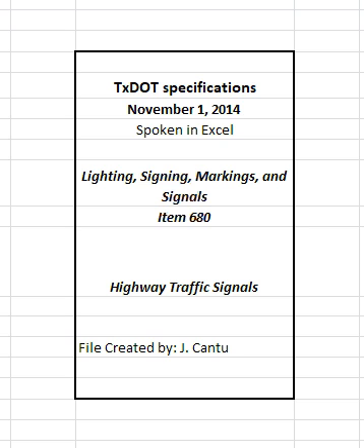Attach ends of wires to properly sized self-insulated solderless terminals. Attach terminals to the wires with a ratchet-type compression crimping tool properly sized to the wire. Place pre-numbered identification tags of plastic or tape around each wire adjacent to wire ends in the controller and signal pole terminal blocks. Splices will not be permitted except as shown on the plans, unless each individual splice is approved in writing. Make all allowed splices watertight.